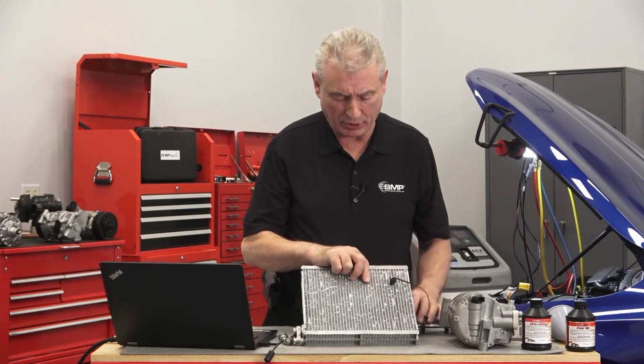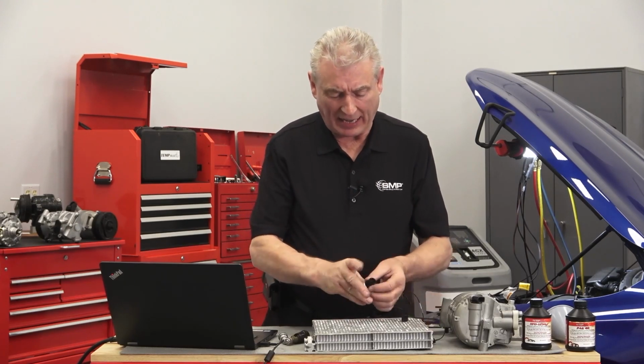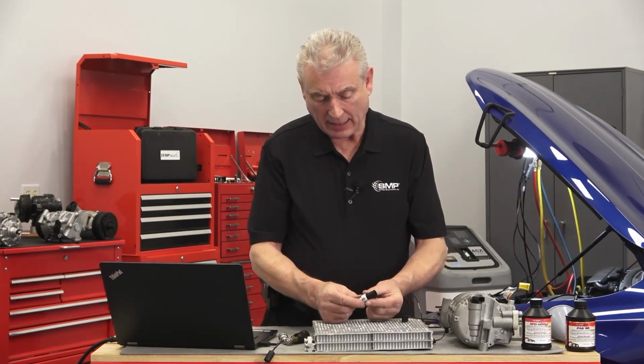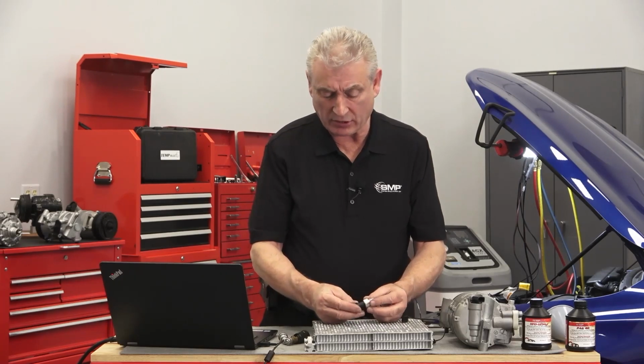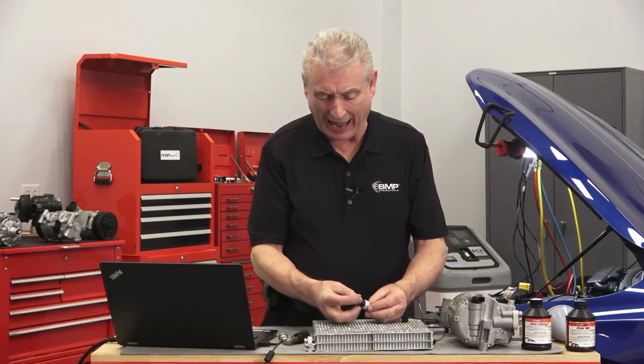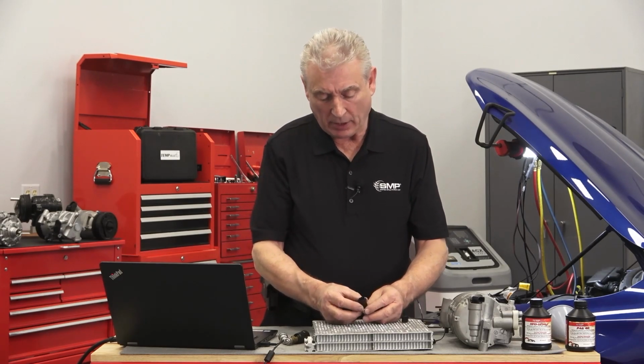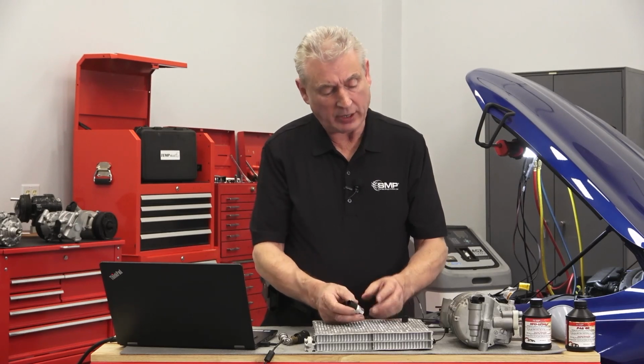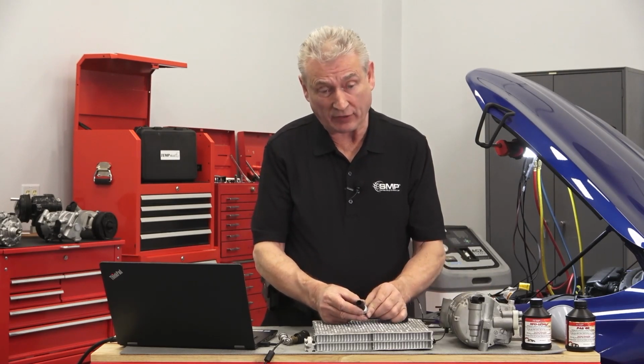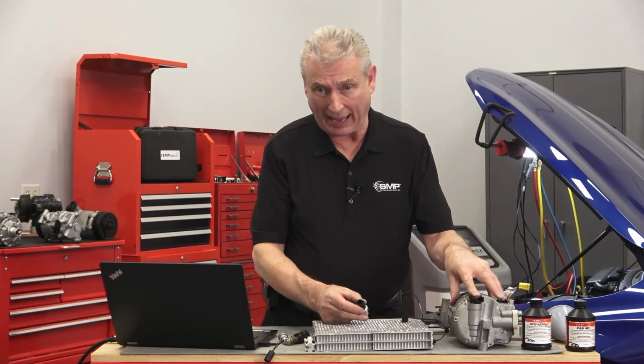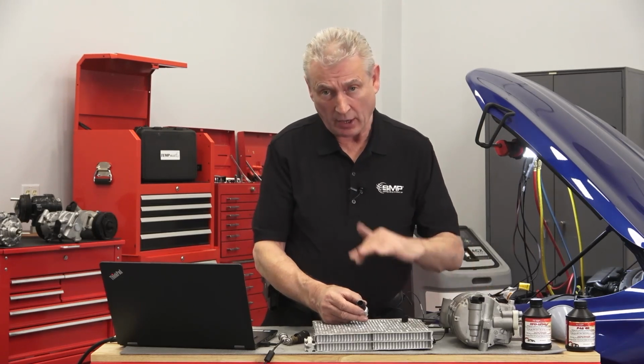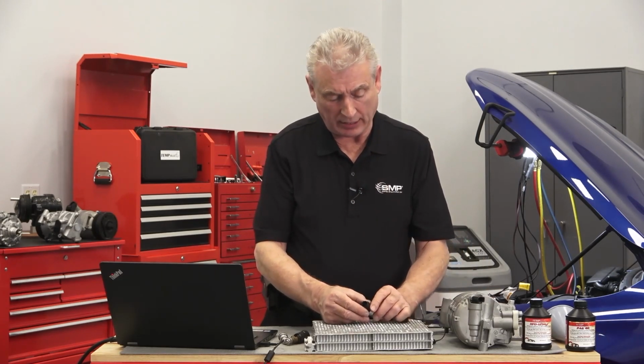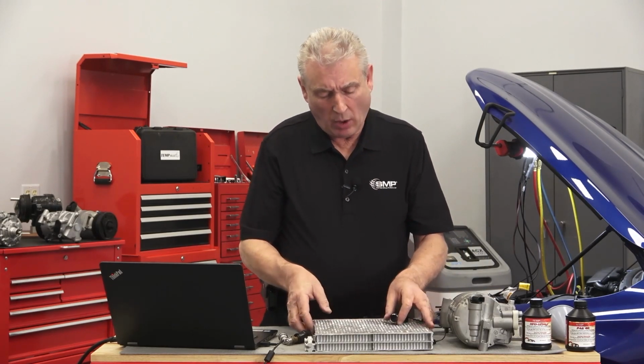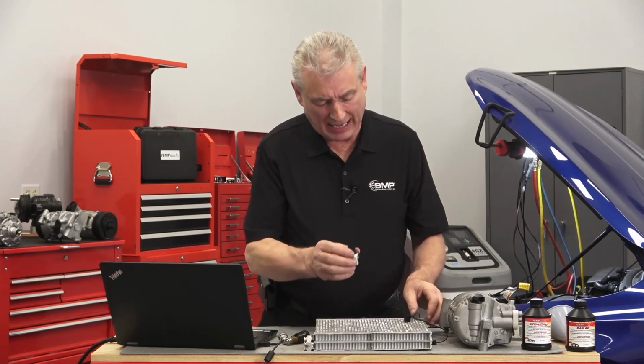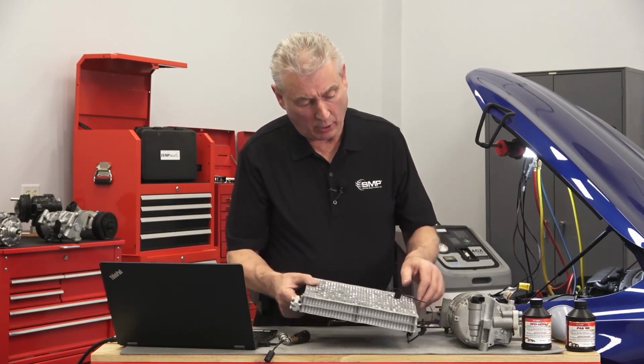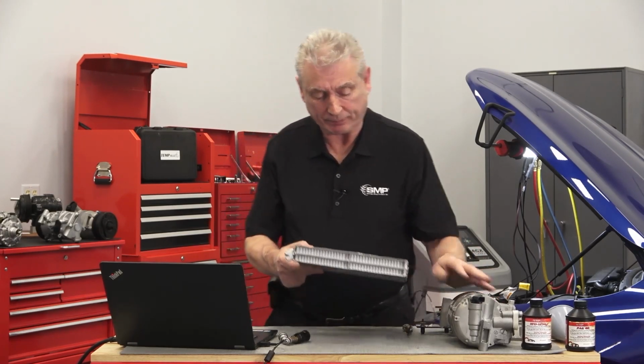Another significant input to the computer is the high pressure transducer. This measures actual high side pressure, and if the pressure gets too high, the computer would reduce the pulse width command to the solenoid to reduce high side pressure in extreme circumstances. So those are the two key inputs to the computer for controlling the compressor solenoid.